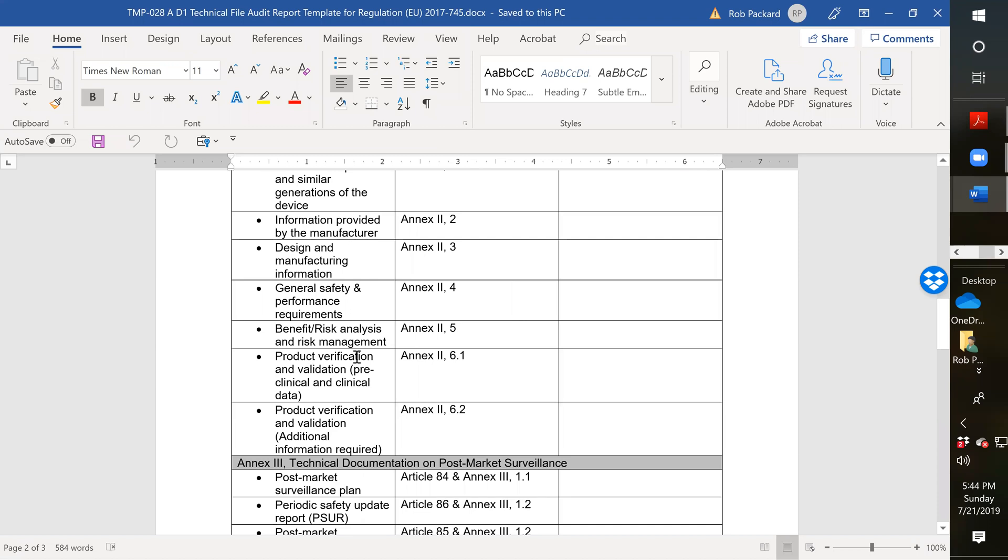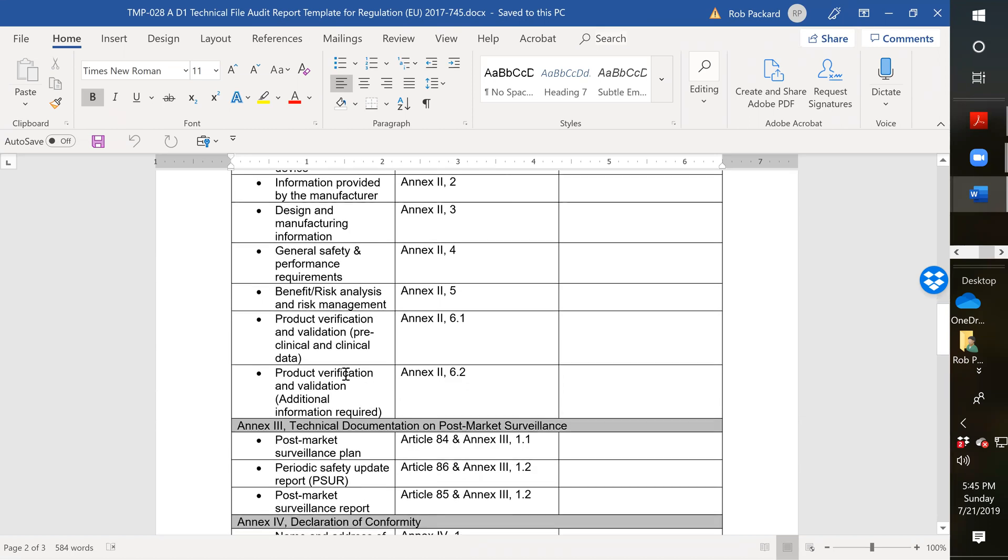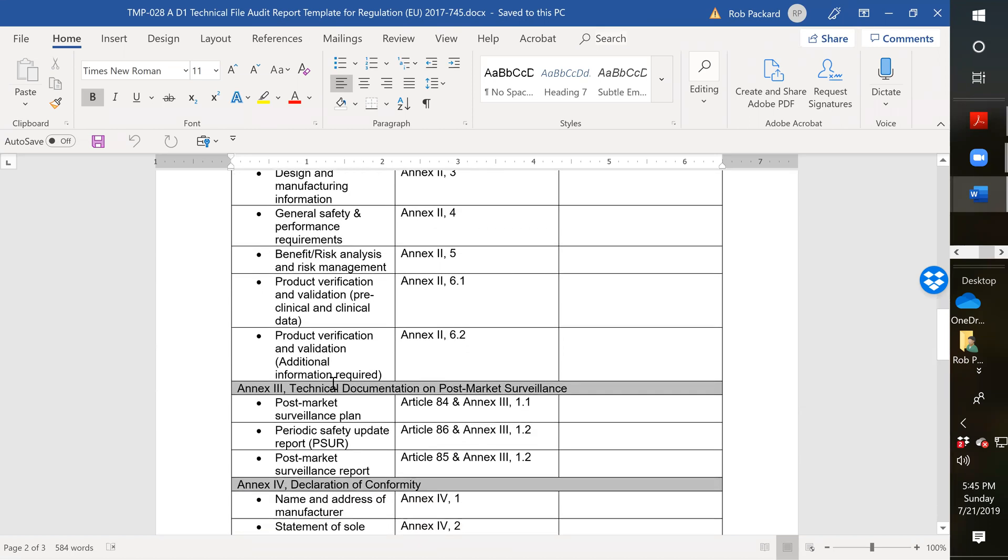The next item is the product verification validation. You're going to be doing this, but if you've got clinical data or preclinical data or clinical evaluation reports, those need to be updated to the latest requirements. And then we have verification validation, additional information that might be specific to that product if there's a common specification. In the past, everything was based on harmonized standards. Now we also have to worry about common specifications as those arise. So you can have common specifications and harmonized standards.